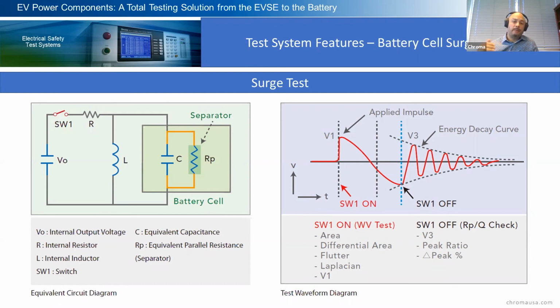One thing that we do, the lead acid battery cell resonates with the internal inductor. Based on the internal inductor, it'll tell you whether it's a good cell or not, right? So we have the applied impulse, and then we have the energy decay curve, which will be the actual impulse that we're going to be testing every single time. Again, we're testing between the positive and negative, which is the insulation that we're testing, making sure the separator between the two is not shorted. Also, this is detected before the electrolyte injection, so it can reduce your defective production rates.